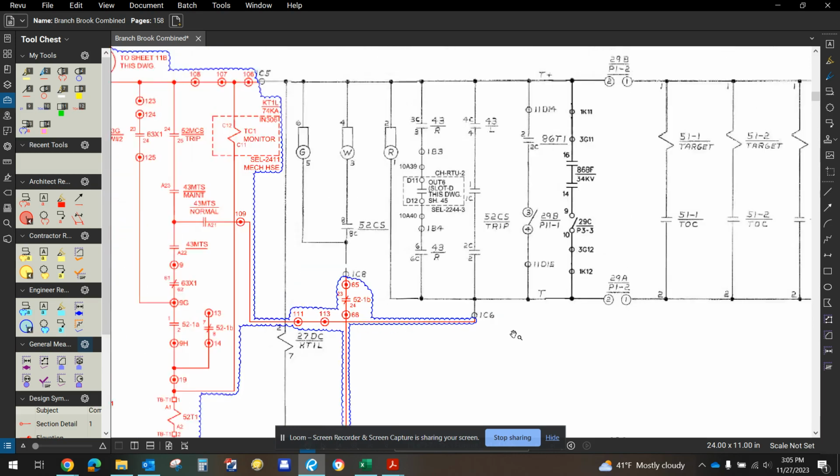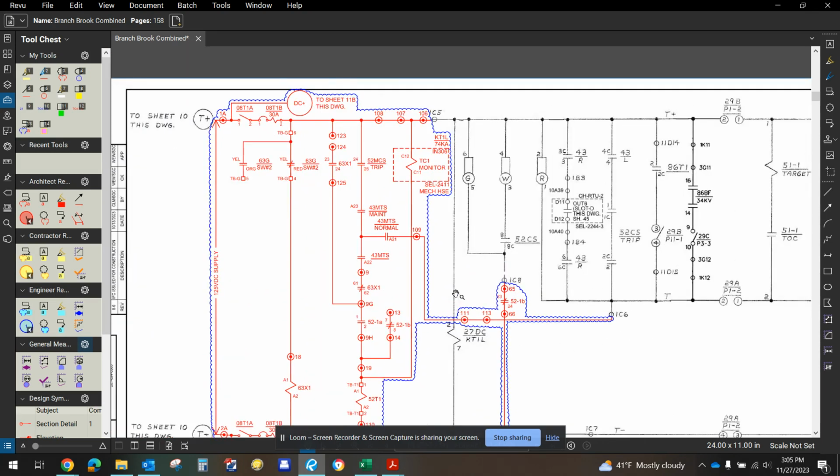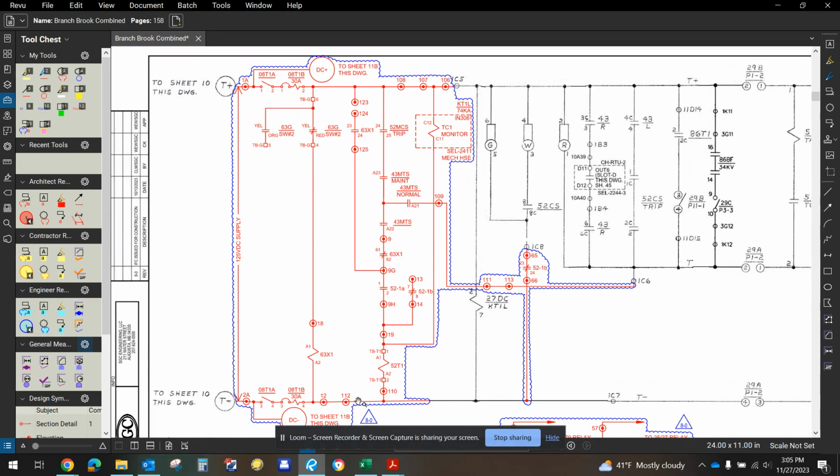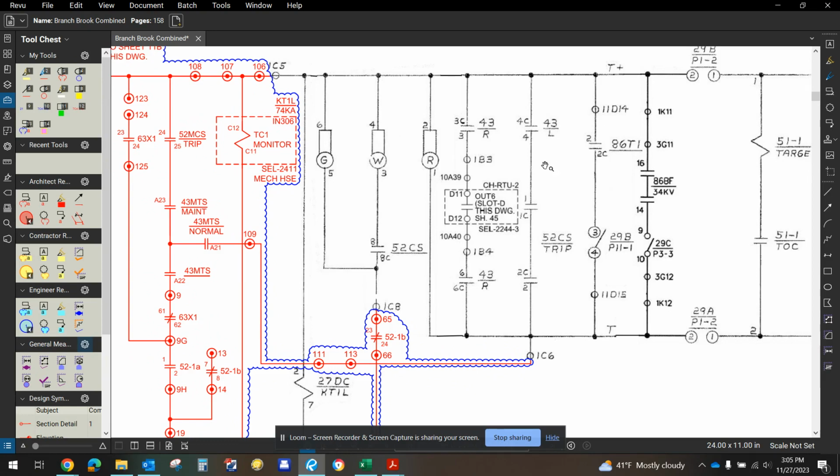When I do my actual trip testing, I have to prove everything in this bubble. So as I'm doing that, I'm also going to watch these red lights and green lights operate, which is an additional layer of proof that I didn't disturb anything. I'm going to trip the breaker remotely with the SCADA trip. I'm going to operate and trip the breaker locally with the breaker control switch.